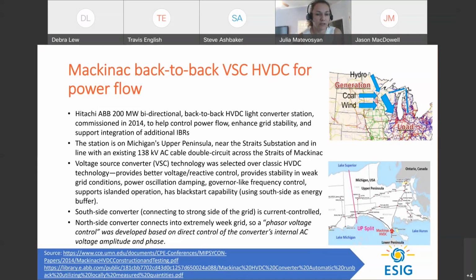This converter station was selected over the classic HVDC technology to provide better voltage and reactive control, provide stability in weak grid conditions, provide power oscillation damping, governor-like frequency control, and also support island operation. It also has black start capability. For black start capability and for frequency control, it is using the Lower Peninsula side of the converter as an energy buffer. It takes energy from the Lower Peninsula to power up the islanded part of the grid during island operation and to provide frequency control. The south side converter is connected to the strong side of the grid, and therefore they used a current controlled converter station there.